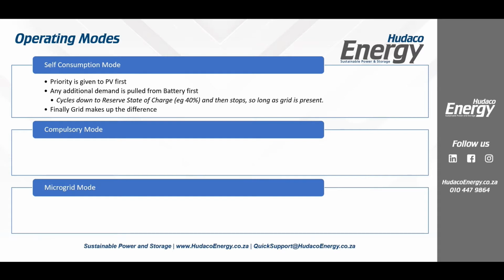So for example, let's say the home was running at 9 kilowatts. It may only be a 6 kVA on the backup loads, but potentially we've got 3 kVA running on our backup loads, and we've got 2 geysers running on my non-essential loads at 3 kilowatts each. We could be having 9 kilowatts through the house. Maybe I've got 4 kilowatts available to us from solar. In fact, I can discharge batteries up to 10 kVA if I wanted to. So we could run 9 or 10 or 11 kilowatts on a home completely on a 6 kVA inverter with our PV panels, with battery, without importing 1 cent from grid. Okay, that's really, really important to remember that. In fact, it's actually a 13 kVA inverter that just runs 6 kVA on backup loads when it's required.